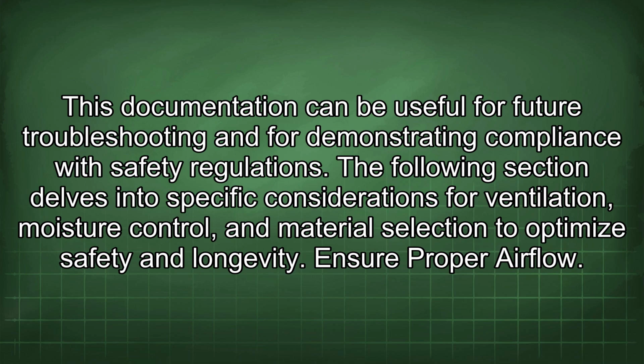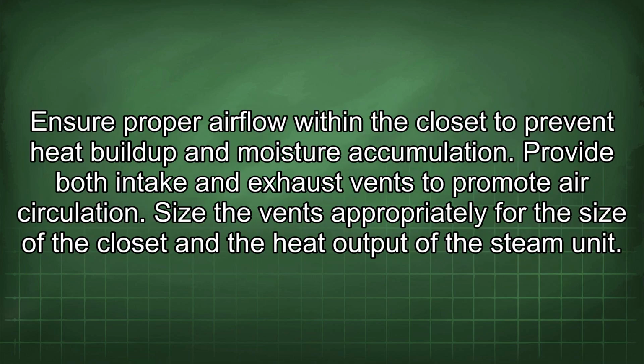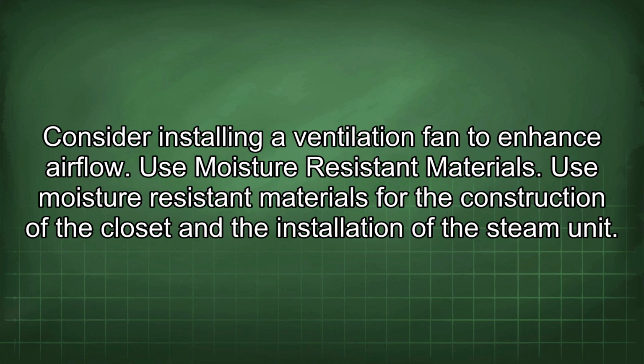The following section delves into specific considerations for ventilation, moisture control, and material selection to optimize safety and longevity. Ensure proper airflow within the closet to prevent heat buildup and moisture accumulation. Provide both intake and exhaust vents to promote air circulation. Size the vents appropriately for the size of the closet and the heat output of the steam unit. Consider installing a ventilation fan to enhance airflow.